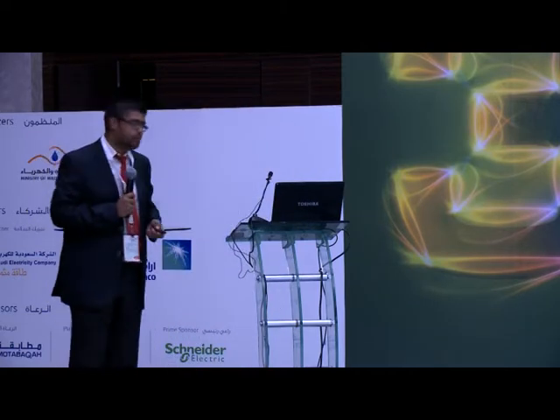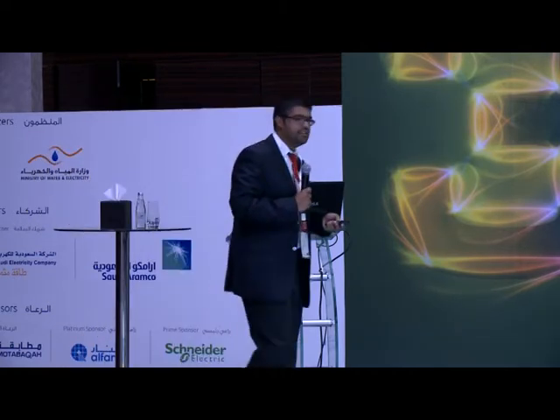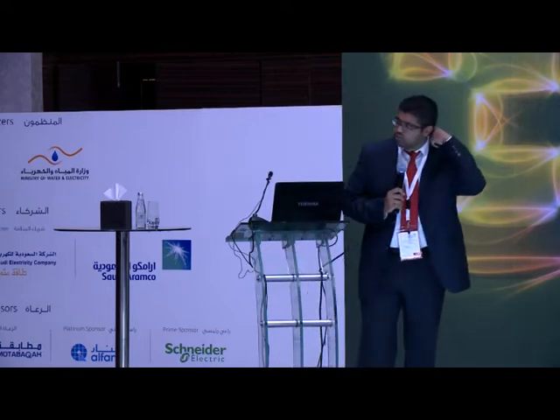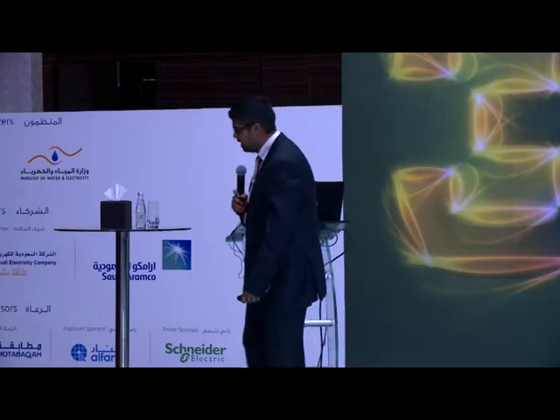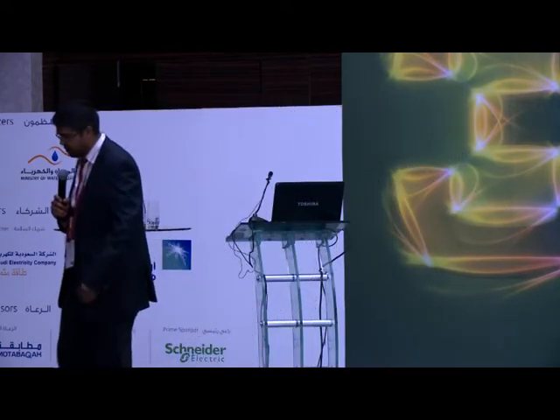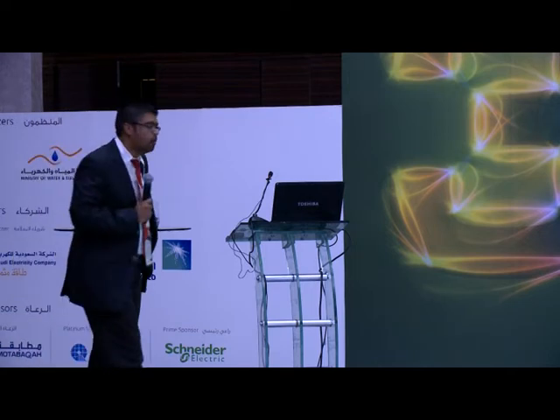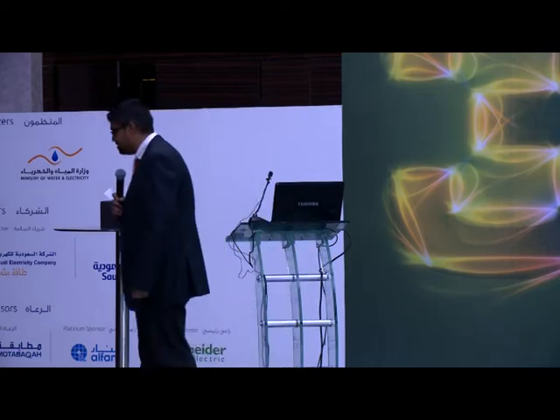Okay, so let's start off with habit number 1. Habit number 1, we talk about dielectric gloves. And dielectric gloves, there's 2 internationally renowned standards. One is the ASTM D120 standard, which pertains to the use of dielectric gloves. And the other is the IEC 60903 standard. And both of these standards refer to classes of gloves. And you would have seen there was a demonstration here next door where your class 00 glove is good for 500 volts AC or 750 volts DC.